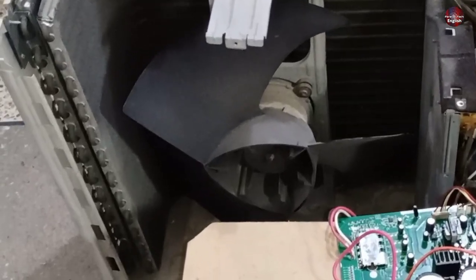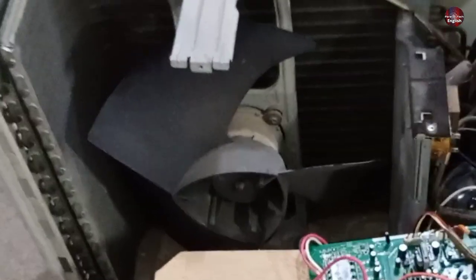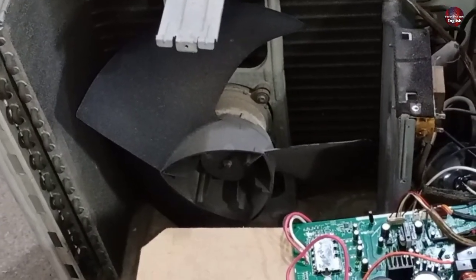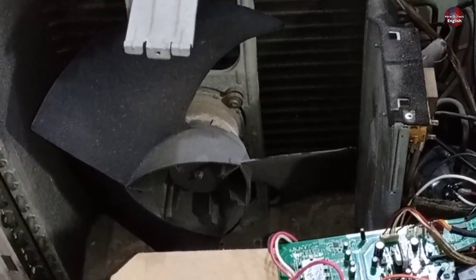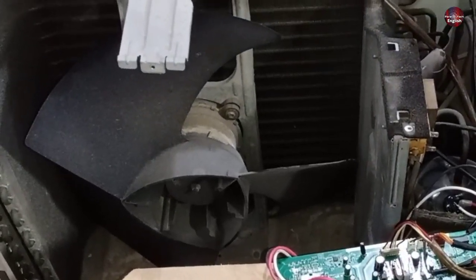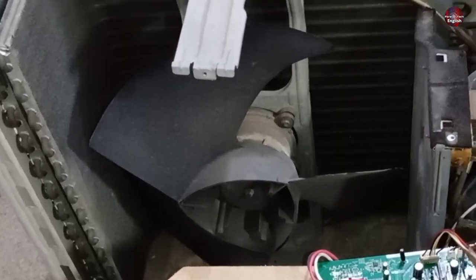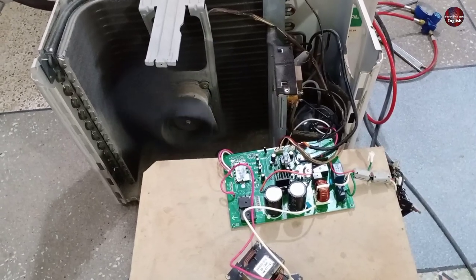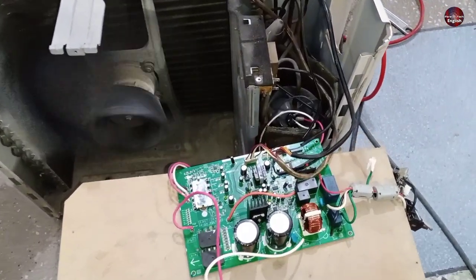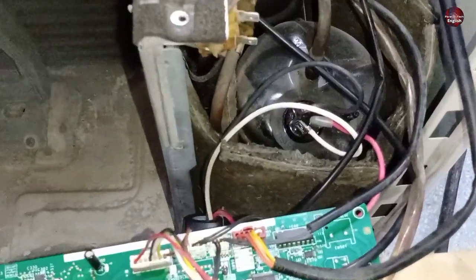So what happens is that the fan motor starts the first, 5 seconds before the compressor, and as in the start of the video, you saw the compressor started first and then the fan, and suddenly stopped while working. But now we have fixed it together. See, now the fan is working first, and after 3-4 seconds, the compressor has also started.